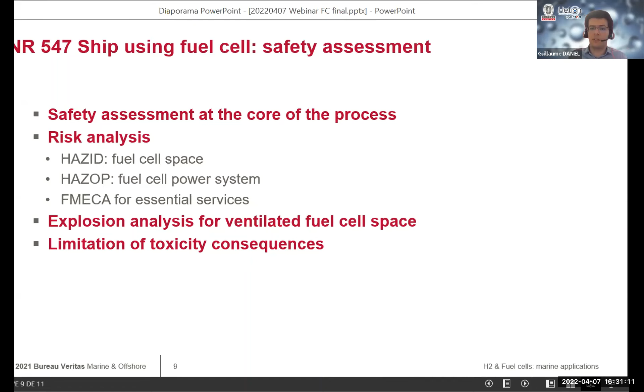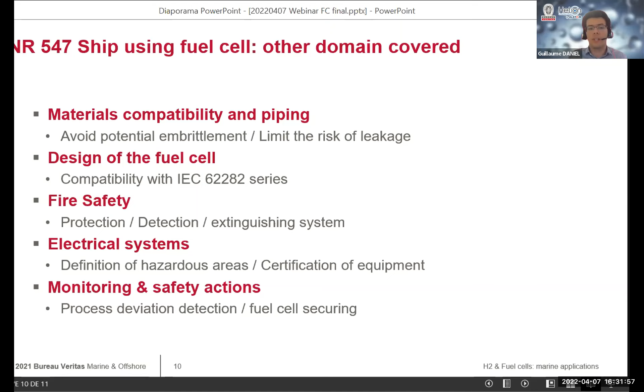So you have to take all those aspects into account. I will go quickly through the other domains that are covered - many different aspects, for example material compatibility, because at some point in general you have hydrogen inside the fuel cell, so with hydrogen we have embrittlement risk that can lead to leakage. There's always an issue. You have elements of the design of the fuel cell, fire safety, detection, extinguishing systems, the definition of the hazardous area, and a lot of requirements, I would say, on the monitoring system to check if there is a process deviation and safety action to secure the fuel cell. So I won't go any further into the details.